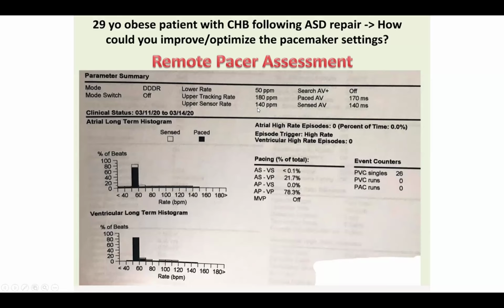So in other words, if the patient starts running a marathon and is really pushing themselves, or is playing soccer and is stopping and starting, and this device senses the activity, it will slowly raise the lower rate as high as 140. Now, interestingly enough, studies have shown that the sensors in most of these devices are very poor, and they don't actually detect motion very well. In most patients it only goes up maybe 10 or 20 beats per minute. The other interesting thing is you can adjust the degree of sensitivity that the device has to activity, and you can make it a little more or less sensitive. And patients are exquisitely sensitive to that if they have been paced in a certain manner their whole life.